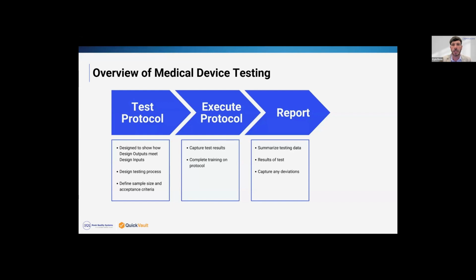Once all the testing is complete, then you summarize all the data, review the results, and describe any deviation. So this report is actually what you will provide to the FDA to show that your device is safe and effective and meets the requirements that you've identified internally as well as any requirements defined by the FDA. And this report will be your record showing this testing to the FDA.